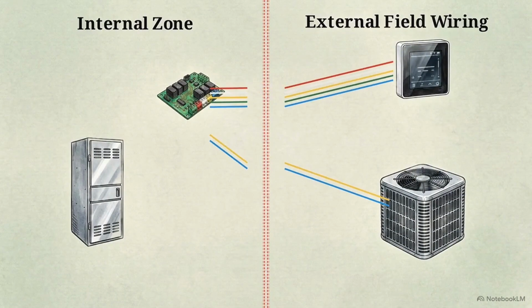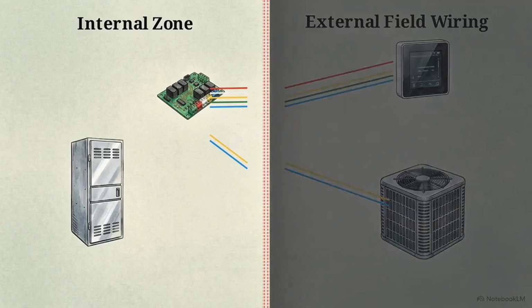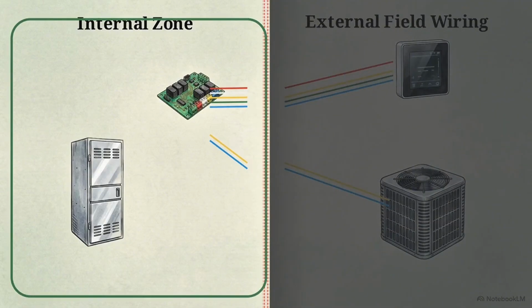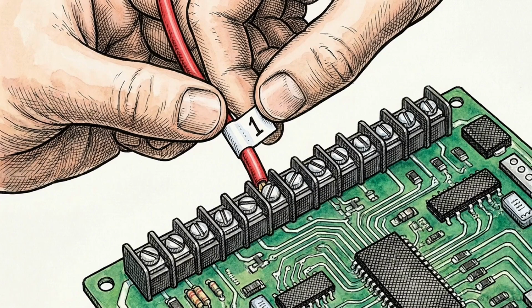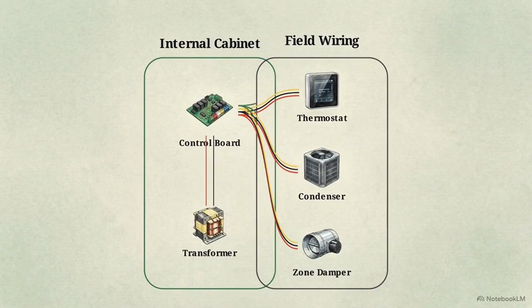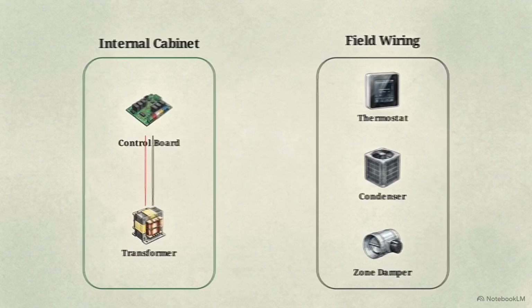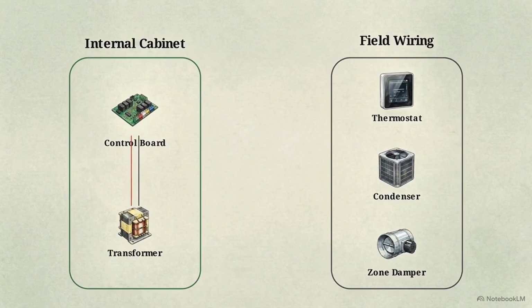We need to separate the internal cabinet components from all external field wiring. Patiently apply labels to every low-voltage wire on the board before you remove them. Trusting your memory here is a fast way to cross wires and introduce a new fault during reassembly. This diagram illustrates the separation. With the power off, disconnect all external low-voltage loads. Remove the thermostat wires, detach the outdoor unit control wiring, and disconnect any zone boards or external accessories. Now, restore power with only the internal wiring connected.